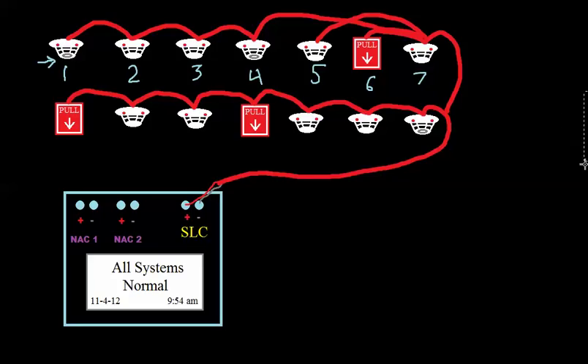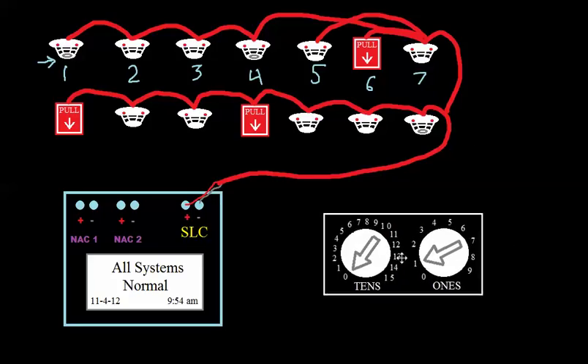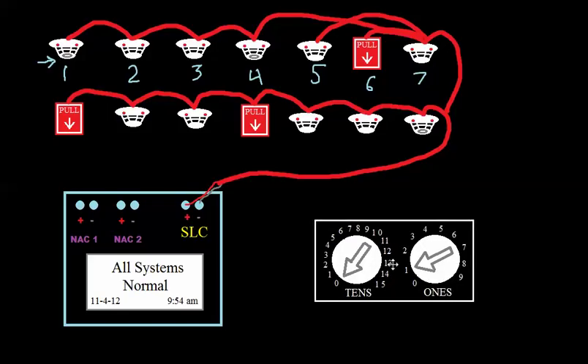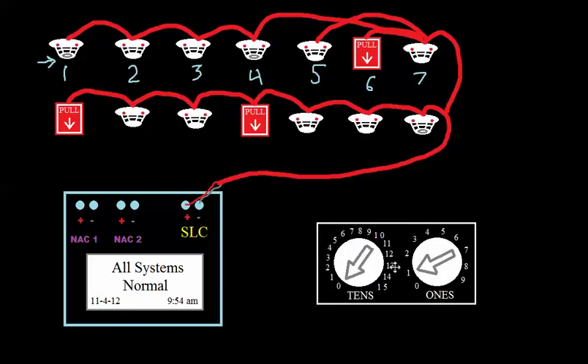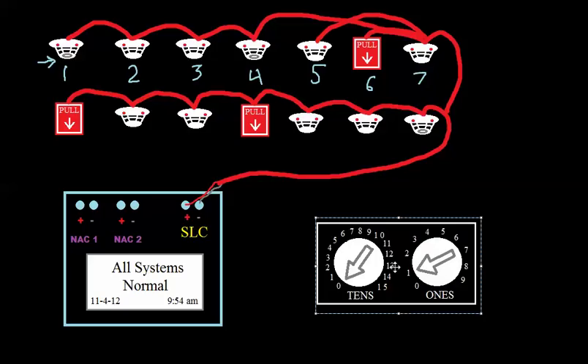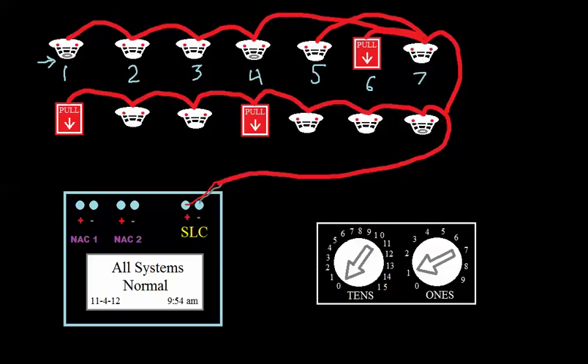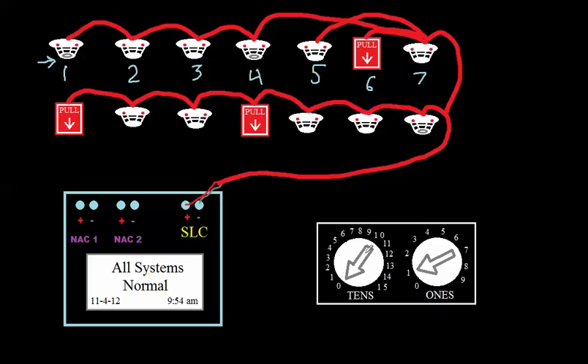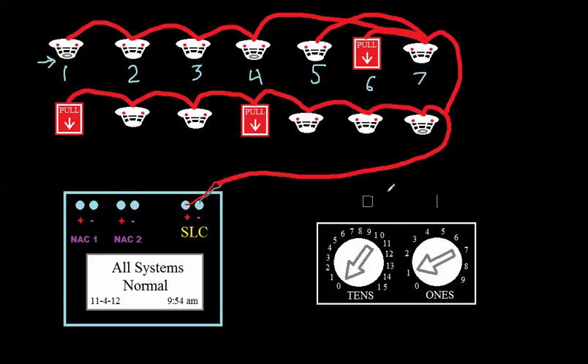I'd have to set an address on each one of those, and I'm going to show you how that works with most panels. I'm basically going to be drawing a lot of stuff that relates to Fire-Lite and Notifier because that's what I'm used to. On all the panels, you have to somehow give these an address, but it varies how you do that from manufacturer to manufacturer. But for Fire-Lite and Notifier, this is typically how it's done. You see these two dials, and this would be on the back of the devices, or in some cases on the pull stations, it would be on the front of them. There's a tens place and a ones place. The tens place goes all the way up to 15. The ones place goes to nine. If I wanted to set a heat detector at device one, I'd leave the tens place at zero, and I would make the ones place a one. So now the address is zero-one. If I wanted it to be 159, I'd set the tens place at 15, and the ones place at nine. It'd be device 159.